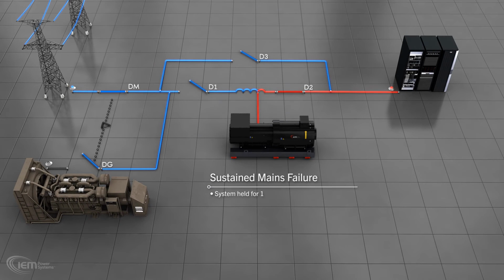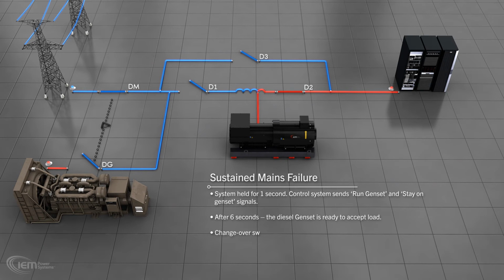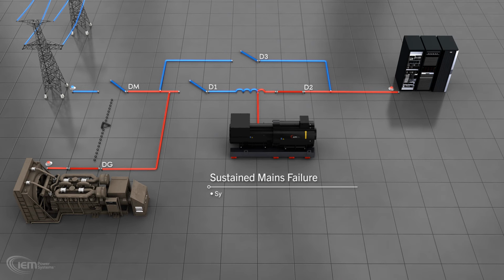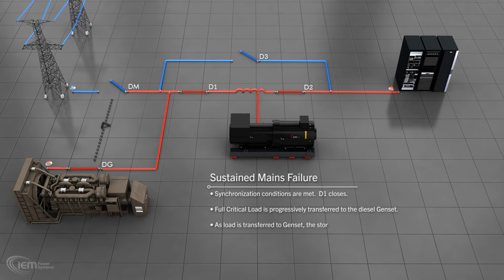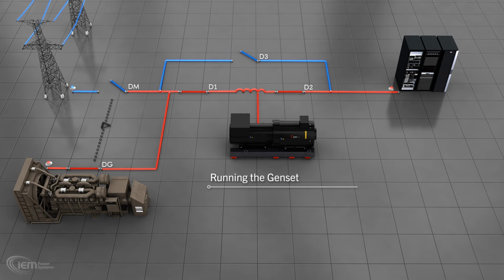After holding the system for 1 second, the control system sends run genset and stay on genset signals. After about 6 seconds, the diesel genset is ready to accept load. The changeover switch operates to open breaker DM and close DG. The control system monitors the phase angle and frequency of the load and the genset, managing the synchronization across breaker D1. As soon as the synchronization conditions are met, D1 closes and the load is progressively transferred to the diesel genset until it supplies the full critical load. During the transfer of the load to the genset, the storage drum gradually slows down until it is near parity with the shaft speed.